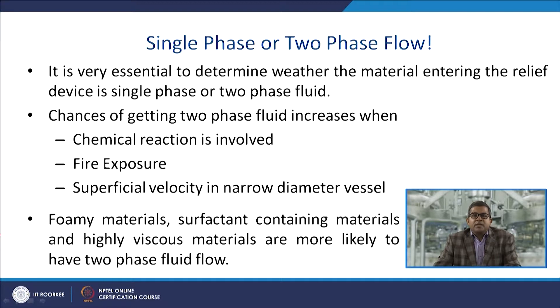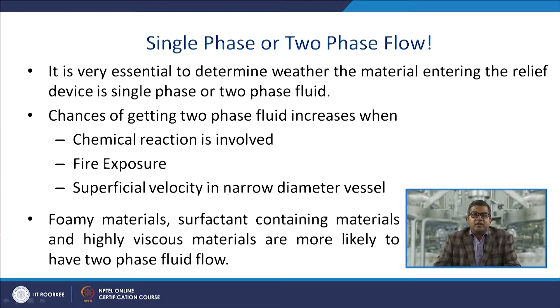It is essential to determine whether the material entering the relief device is single phase or two phase. Chances for two phase fluid increase when there is a chemical reaction involved, fire exposure, high superficial velocity in narrow-diameter vessels, phase transformation, foamy materials, surfactant-containing materials, or highly viscous materials.